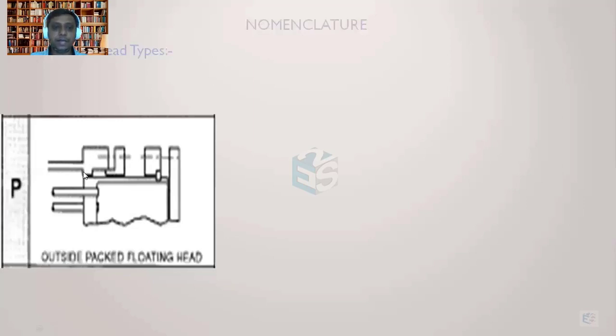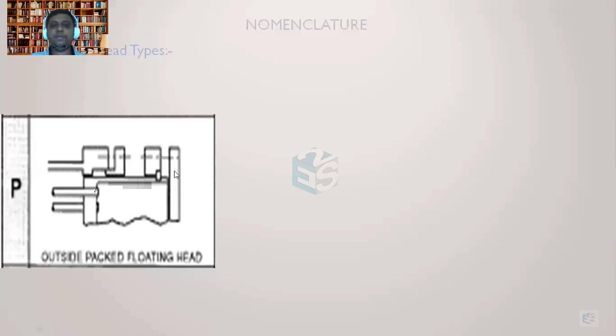A flange is welded to the main shell, and it has a pocket or groove where packing is placed. The packing touches the tube sheet and the channel shell from outside, resting inside the groove. The other flange has a male recess. When the stud and nut assembly is tightened, the two flanges come closer and the packing gets compressed on all sides — against the faces of the flanges, the tube sheet, and the groove — preventing leakage from any direction.